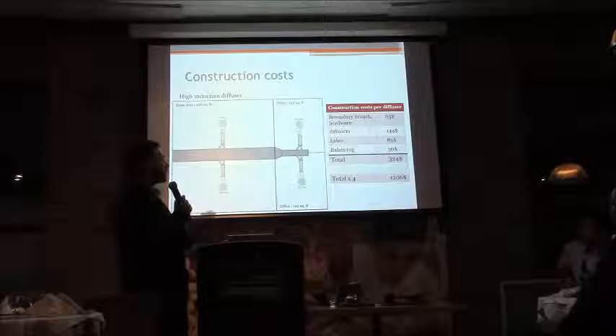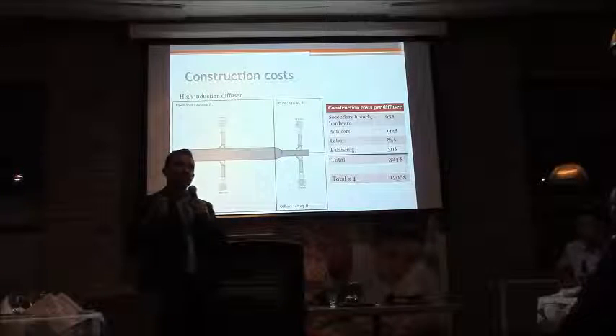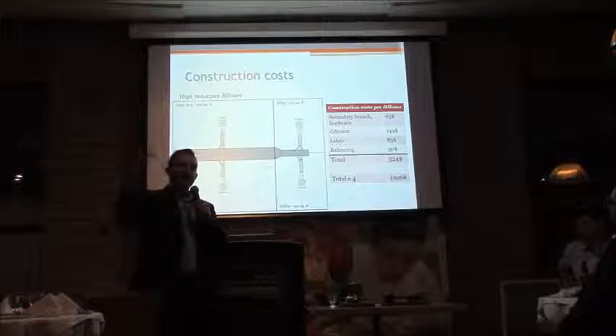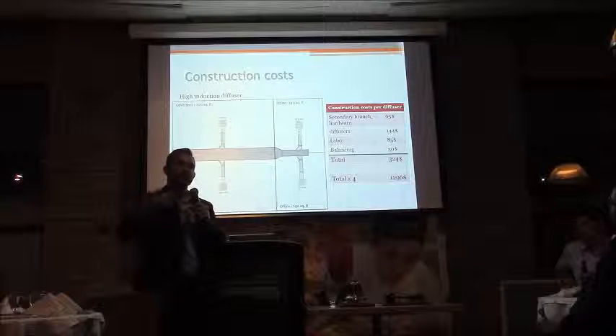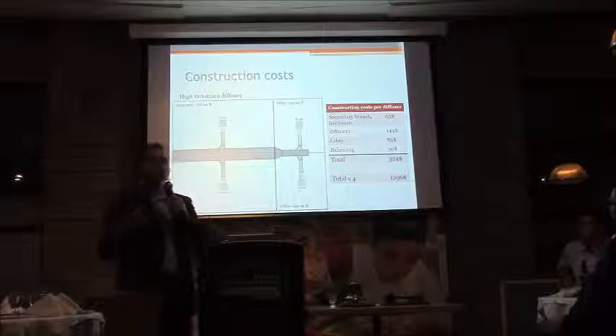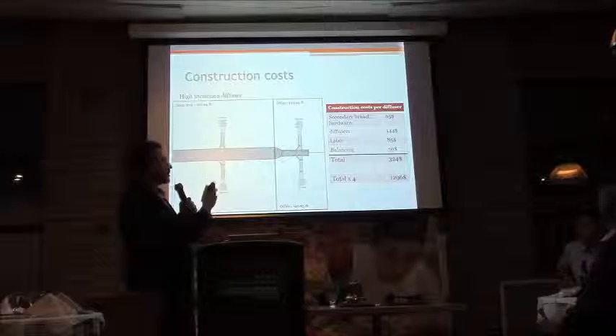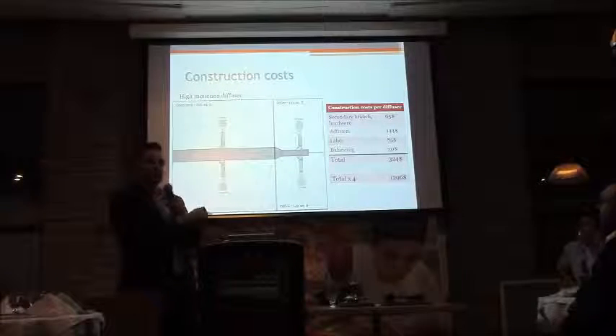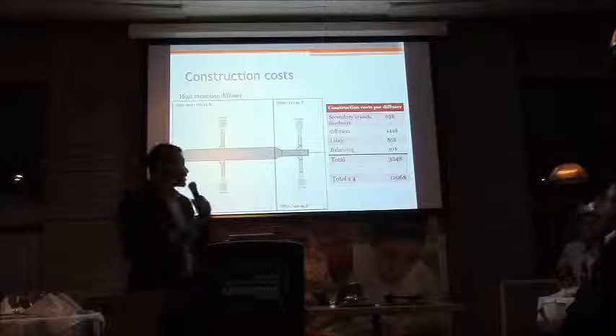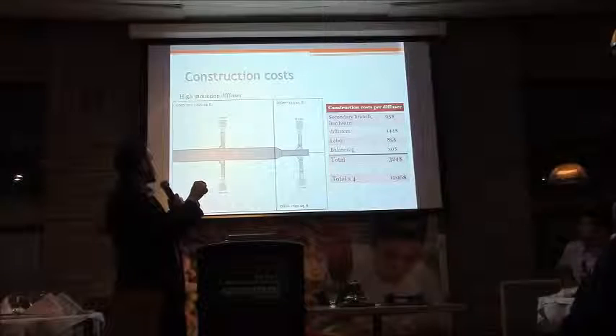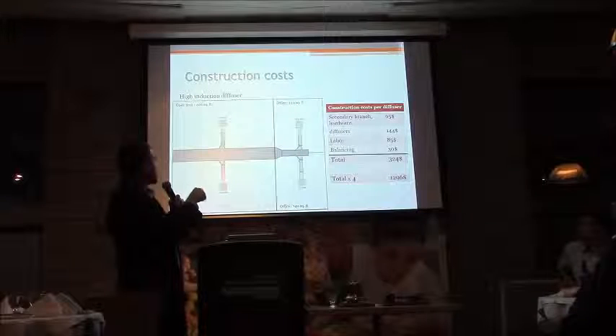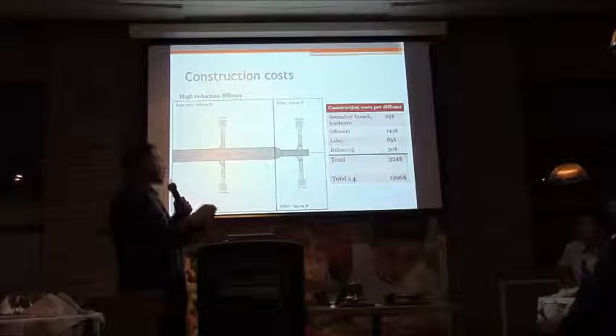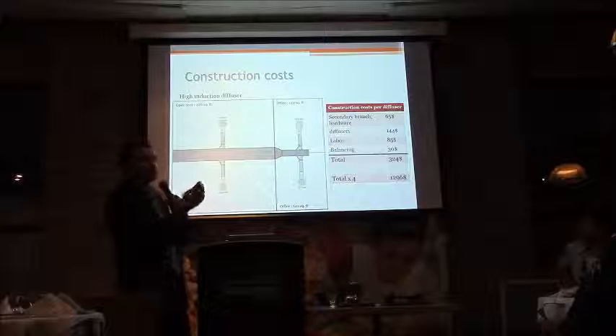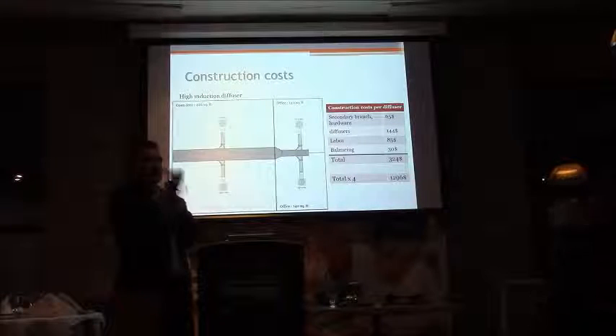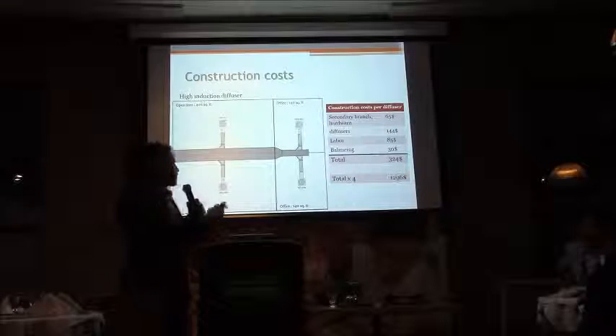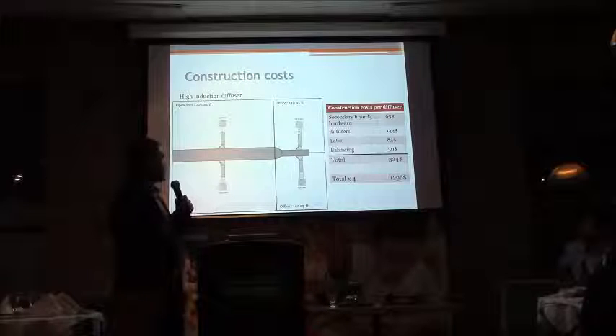The advantage with high induction, because I was mentioning you can use a plenum, so you don't have the added sound values, the added static pressure loss, and it doesn't affect your airflow pattern. So you're able to throw more air into a diffuser without having any negative effect. So we're at 280 CFMs per diffuser, and there's only 2 of them in the open area. Now for the offices, there's not much we can do. It's 1 diffuser per office, so you can't cut a diffuser in half. So it's 1 diffuser per office still here.